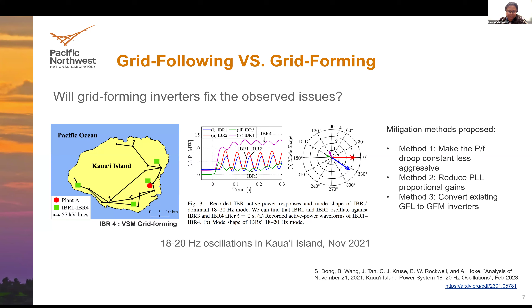responded to it, and that led to around 18 to 20 hertz oscillations that lasted for quite some time in the system. And while this was reported, one of the IBRs was already grid forming, and 3 of them were grid following. And so when NREL did this analysis, they proposed a number of mitigation methods informed by the EMT simulation of the system. And one of the proposed methods was converting existing GFL to GFM inverters. So that was done. One of the IBRs was converted to GFM. So then what they observed a year later, with the GFMs, and these were virtual synchronous machines, is that the 2 GFMs start oscillating against each other at around 1 hertz, so at a slower frequency. But here the magnitude of the oscillation, the amplitude of the oscillation, was much lower.